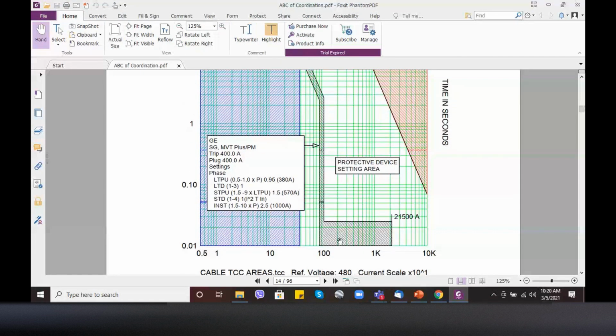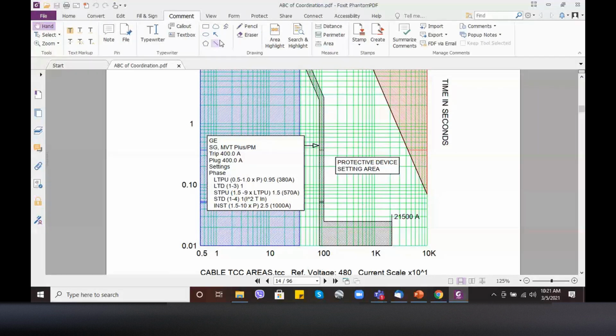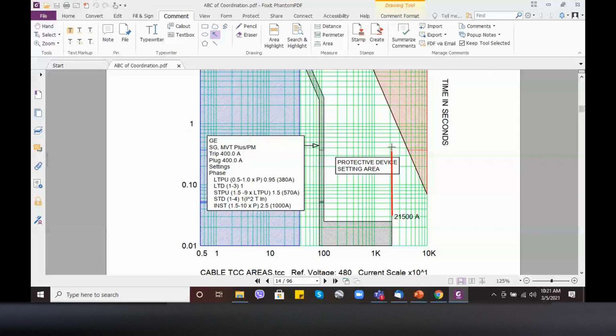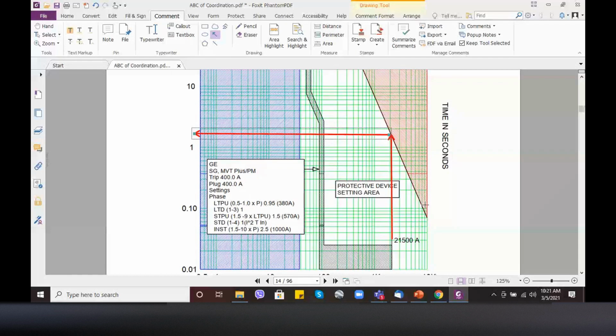Okay? Meron ng 21,500 amperes, no? Just in case hindi nag-trip yung circuit breaker mo with that value of fault current, anong mangyayari? So, ang mangyayari dyan, yung 21,500, i-project mo lang kung saan magi-intersect yung time, no? Intersect yung time, dun siya mag-fail or dun na siya magkakaroon ng insulation failure. So yung 21,500 amperes, pag hindi nag-trip yung particular circuit breaker mo that protects your equipment or cable, mapapansin nyo around 1.5 seconds, your insulation will be damaged.